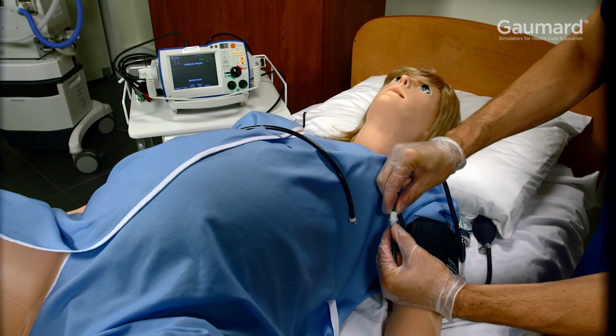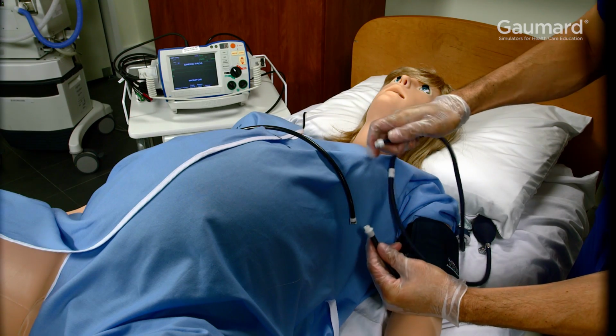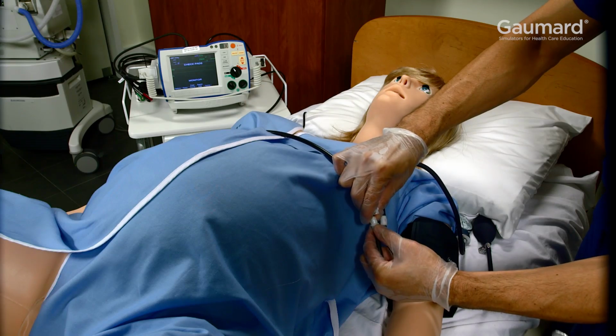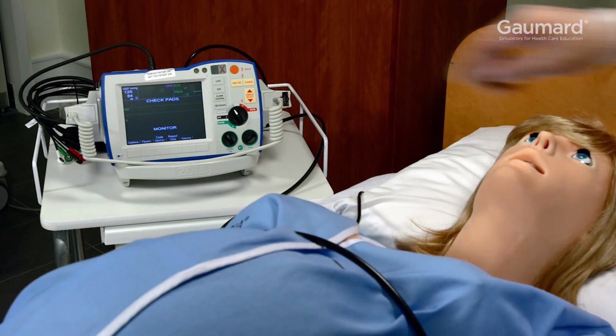After calibrating, plug the blood pressure cuff back into the Auto NIBP machine and measure the blood pressure the same way you would on a real patient.